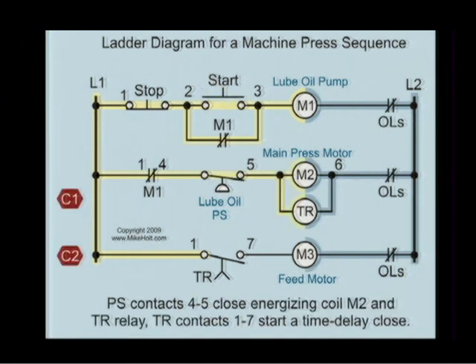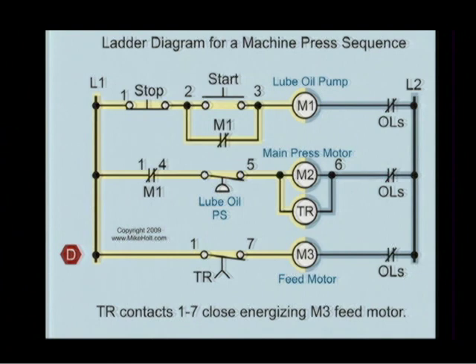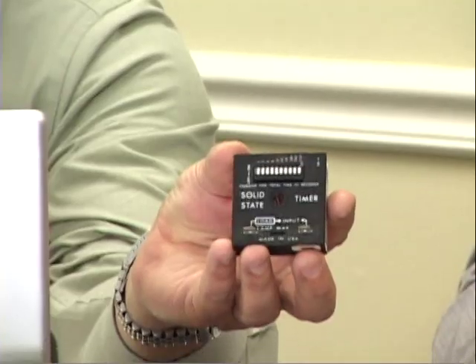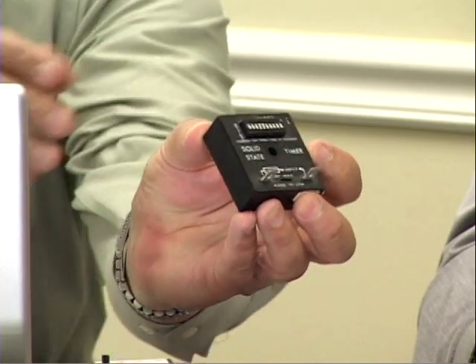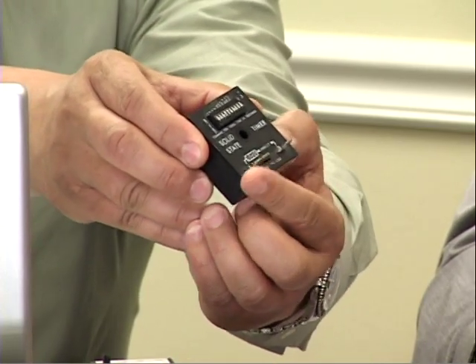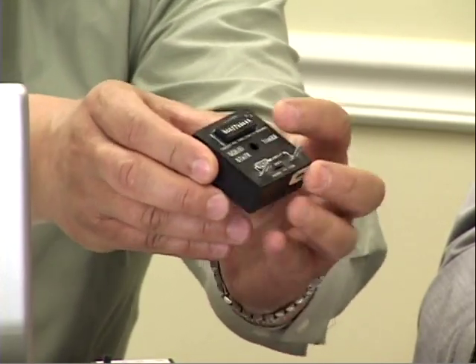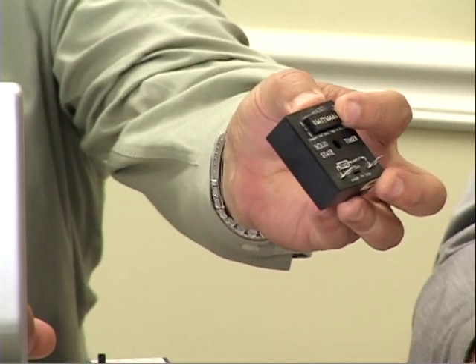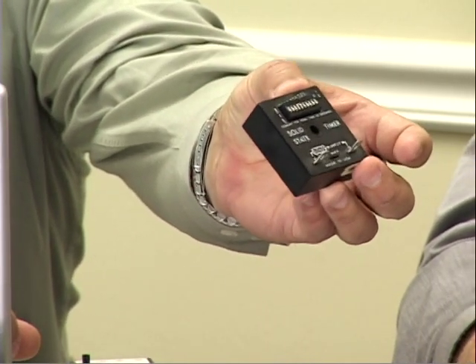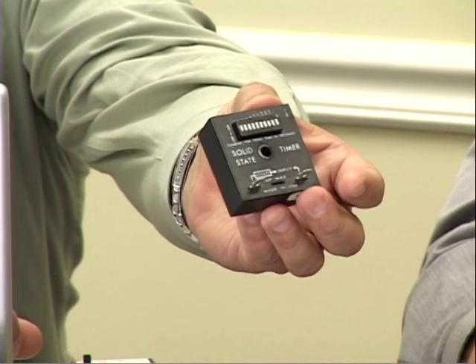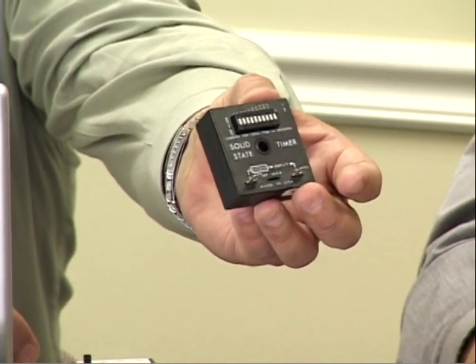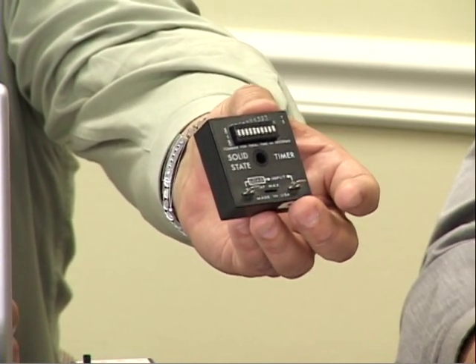And so that's your start. Energize the coil. Here's your lube closing. Energize the second one. Here's the time delay closing, energize, and Mike did a great job of having all these graphics right in order like that so we can see it. Eric, you got a comment there? Yes, this is a small solid-state timer that you can see the contacts here, and it's adjustable with these switches. So tell me more about that. What does that mean?